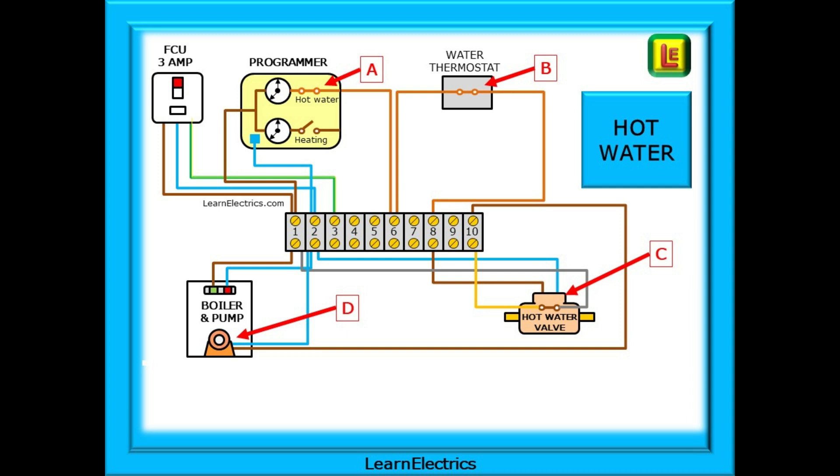Let's strip the system down and look at just the hot water sequence. Power enters the system at the FCU and this should be fitted with a 3 amp fuse, not 13 amps. There is a 10-way connector block and terminals 1, 2 and 3 are occupied with the line, neutral and earth from the FCU. Note that on all these drawings, I have left off the earth or CPC for clarity to make the drawing easier to follow. Please ensure that you install a CPC to all the appropriate places.